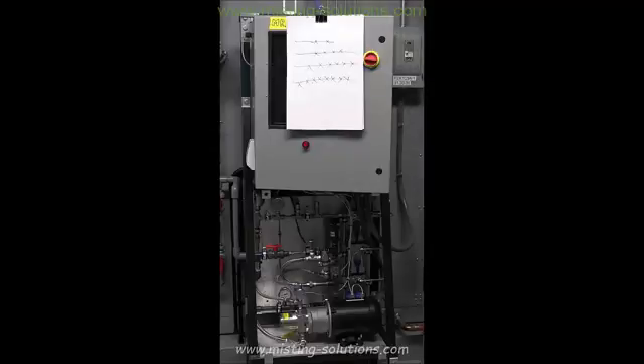Because all these lines go up that high, in order to dump this, we want to go up there and dump it, but we don't want to bring that line all the way down the drain, because then it would want to siphon each zone as it did. So it's open up there to drain, and that prevents it from siphoning. All you're doing is dumping the pressure, not the water. Yeah. And that's more of a safety thing than anything else. If you lose power, they all dump. That's the normally open on that side.